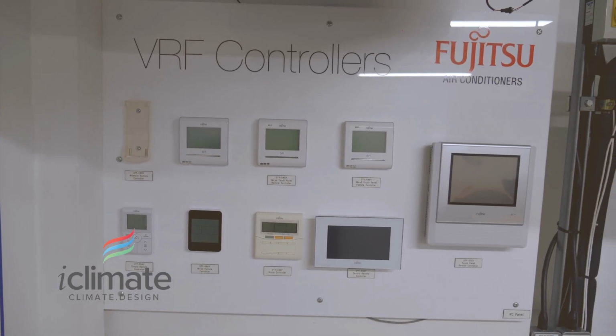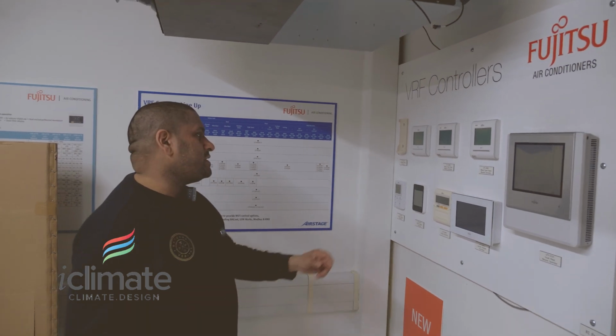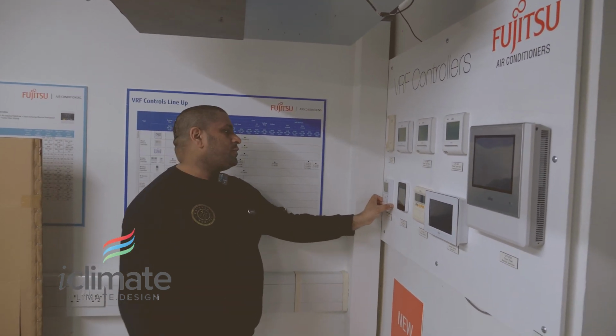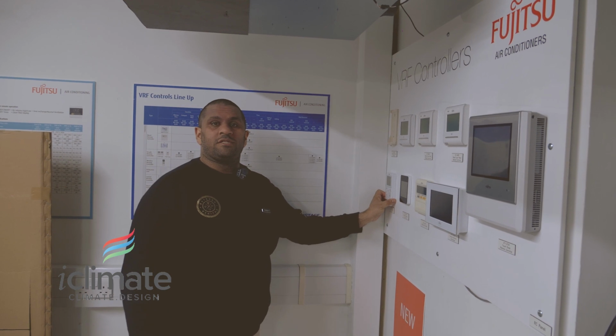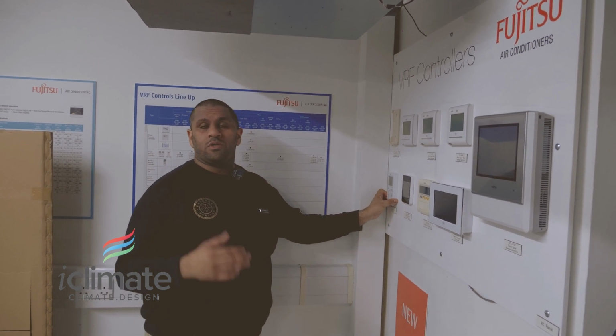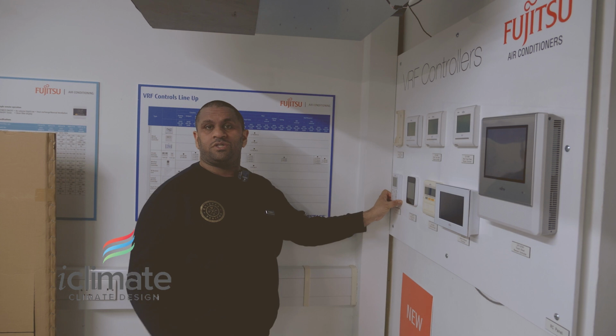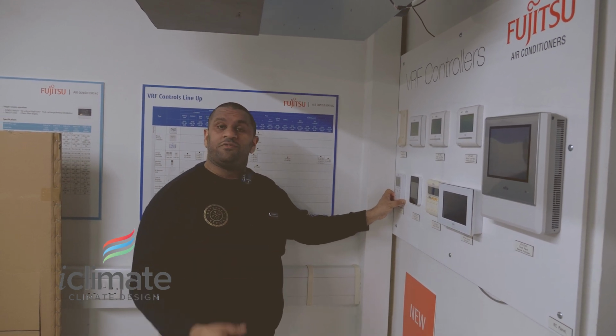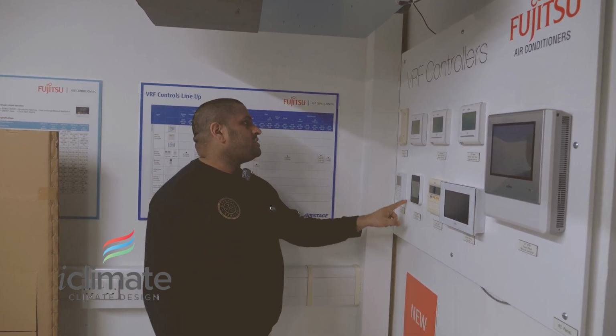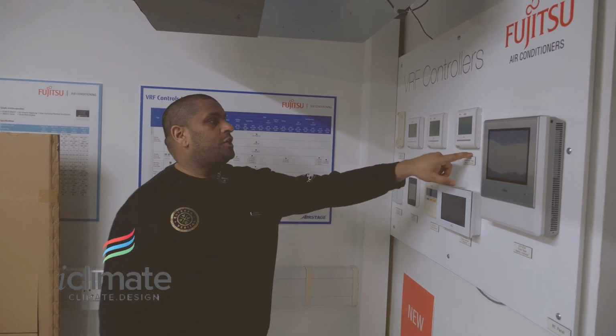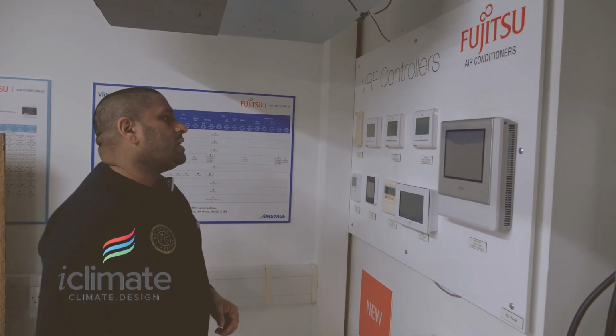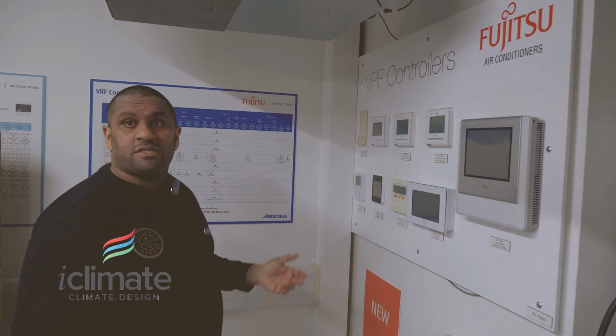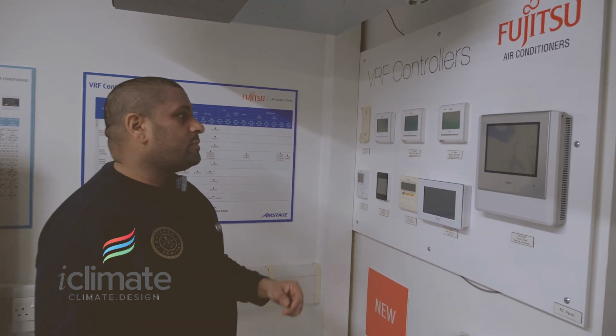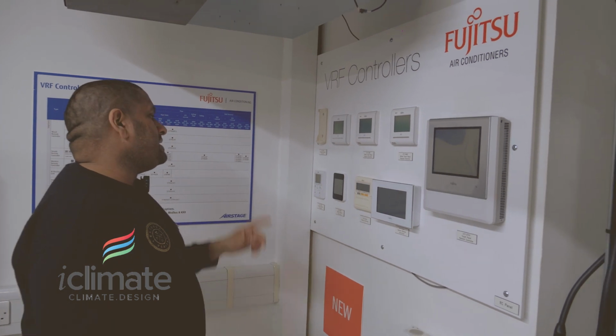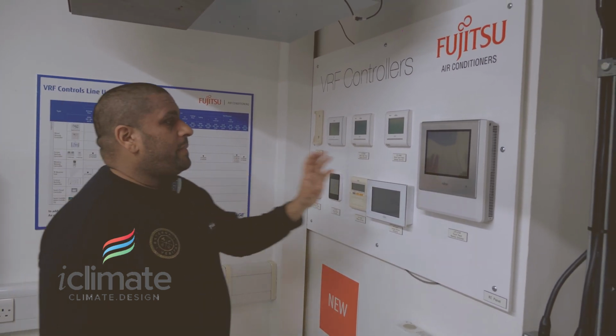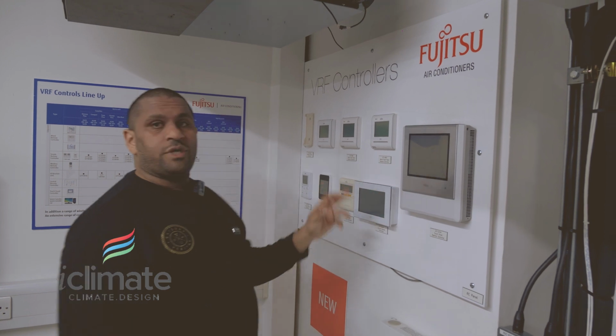There's an array of ways you can do this, and typically what we see with hotel applications is the simplified wall controller. It sits on the wall, very easy to use, and the guests can switch between heating and cooling modes. We can also offer a limited functionality if the hotel wishes to put a type of seasonal energy efficiency cap on the operation. So that's what you see here. Then you can have a range of touch wall controllers, which are more suited to the high-end rooms or the presidential suites, or the private residences within some of the hotels, which give you a bit more functionality than the simplified controller. And the main largest controller here are the two touchscreen options.